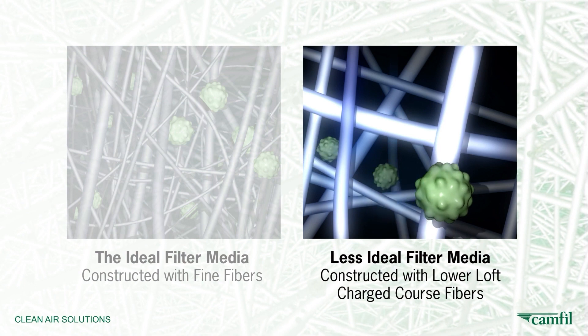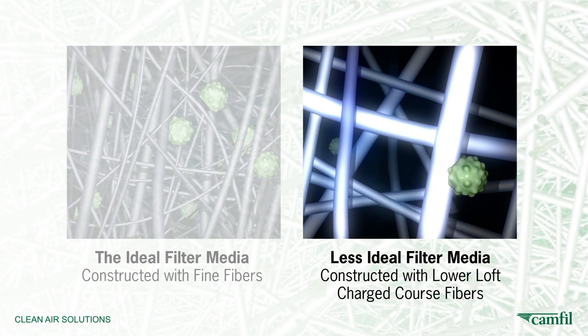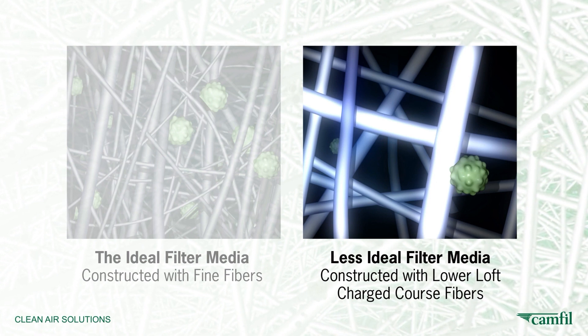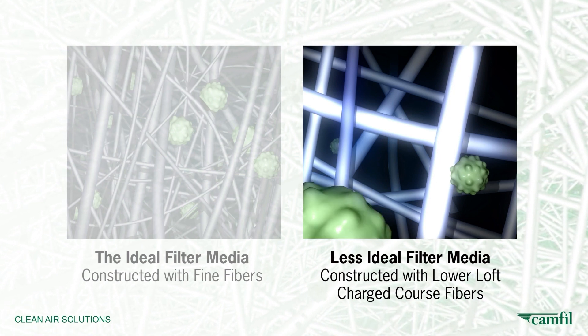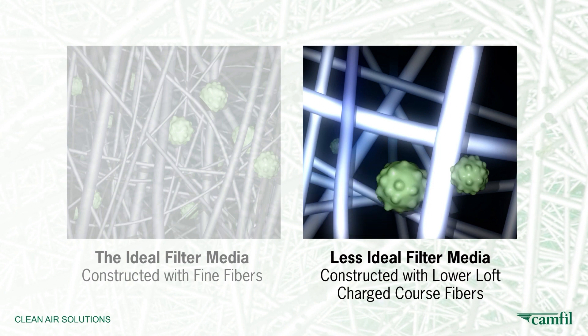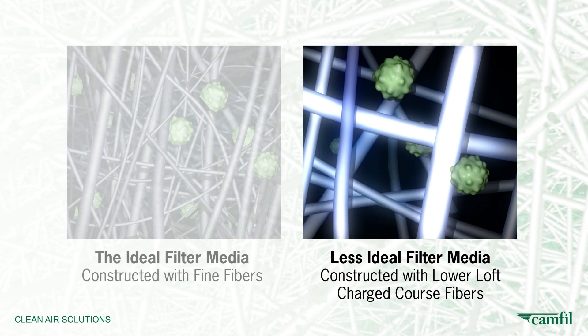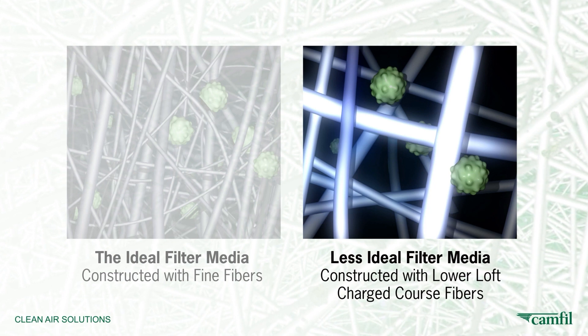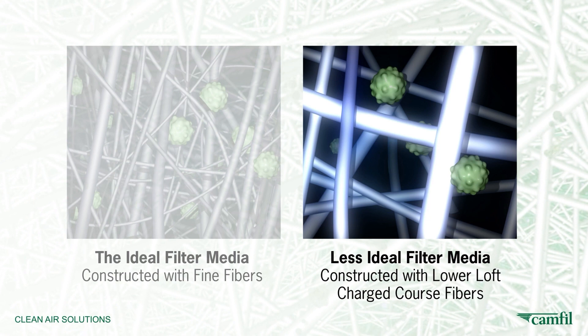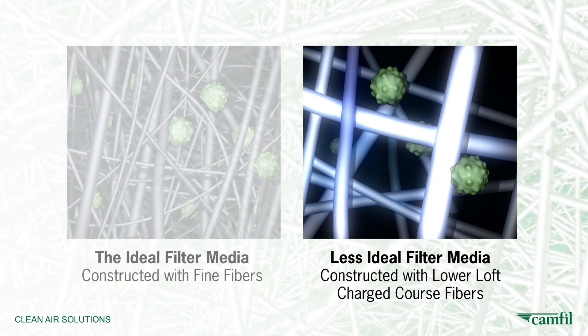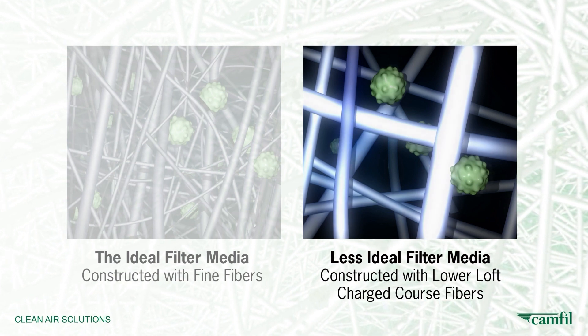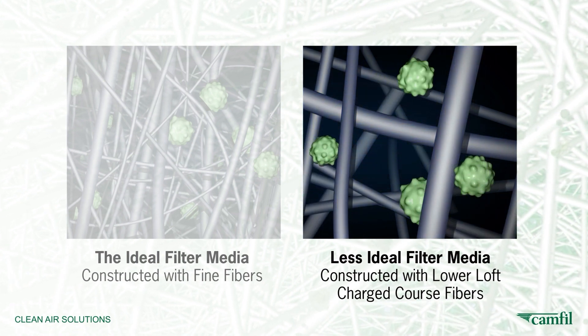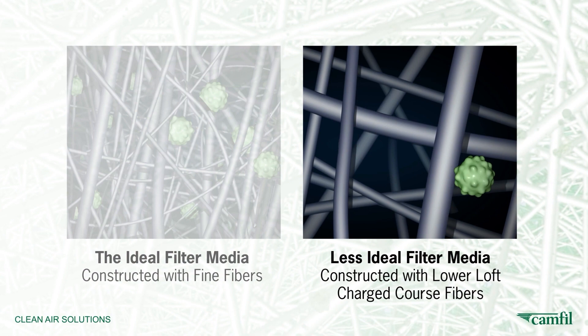A less ideal media consists of larger, coarse fibers, often in a lower-loft non-woven fabric. This type of media achieves a higher MERV value initially by imparting an electrostatic charge on the fibers. The charge acts like a magnet to attract smaller particles to the larger fibers. Electrostatically charged media works well in N95 masks as they are intended for short-term single-use. However, this principle fails when it comes to air filtration because filters are intended to remain in service for prolonged periods of time.